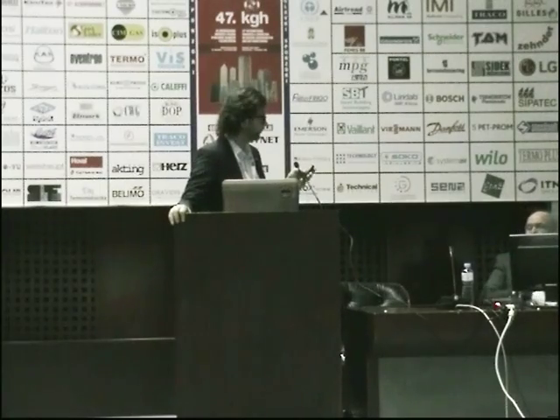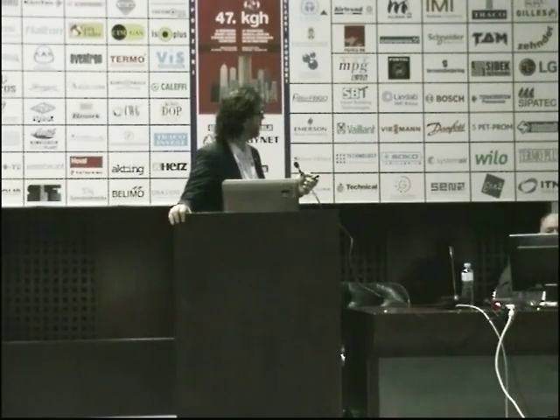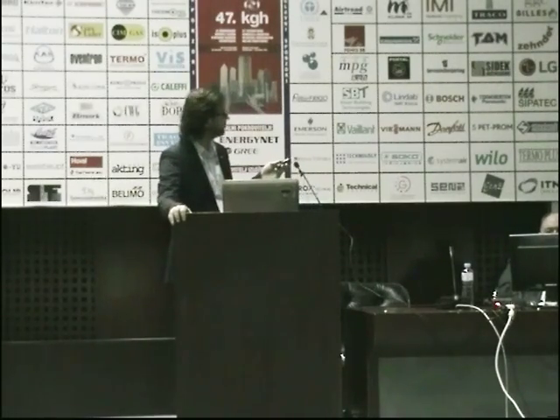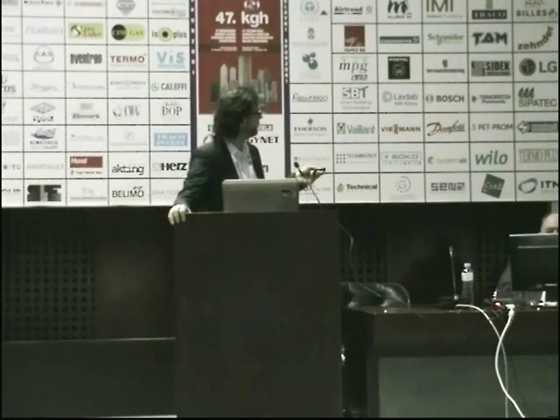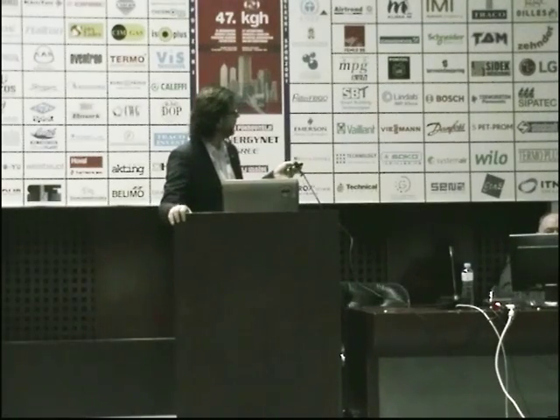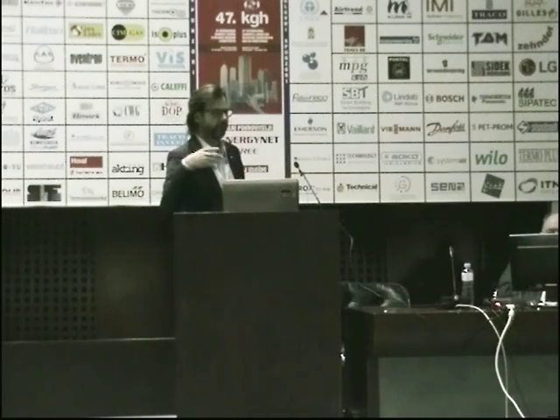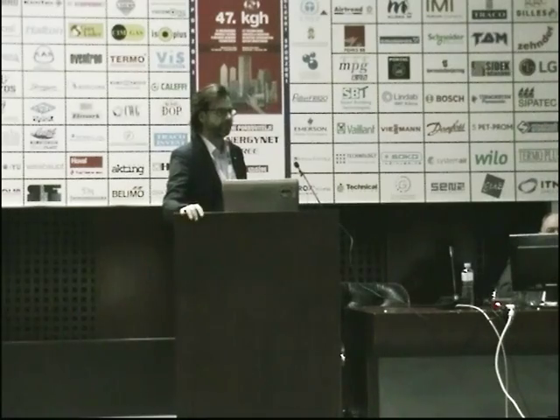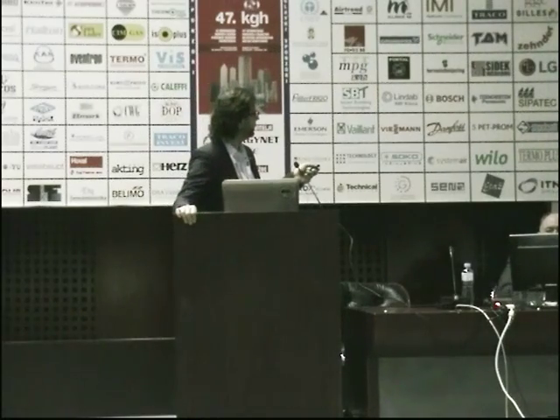These are smaller CO2 compressors, so one is 175 kilowatts each. This is out of the machine room, one hard point. You have the ammonia surge drum, the CO2 vessel, a CO2 emergency cooling. If the ammonia system stops, we cool the CO2 vessel with a small propane unit. And on the back side, you see the heat exchanger for the glycol system.